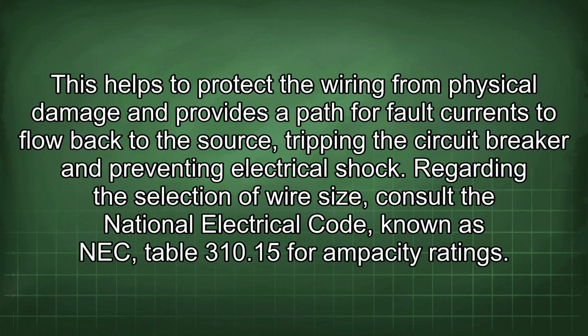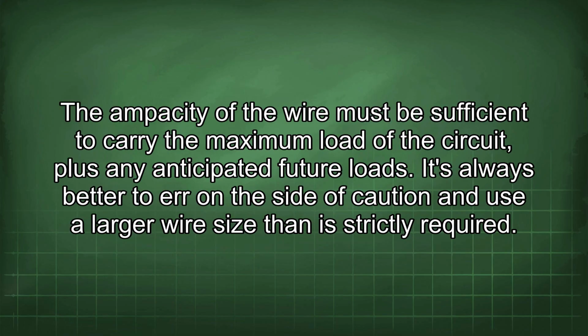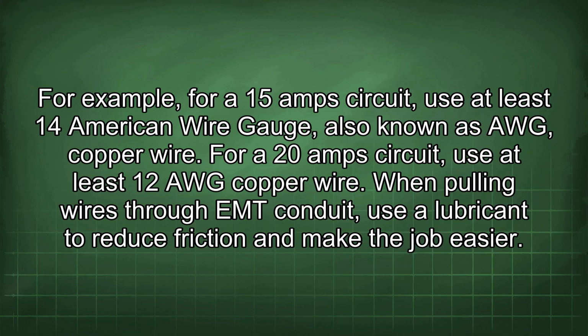This helps to protect the wiring from physical damage and provides a path for fault currents to flow back to the source, tripping the circuit breaker and preventing electrical shock. Regarding the selection of wire size, consult the National Electrical Code, known as NEC Table 310.15 for ampacity ratings. The ampacity of the wire must be sufficient to carry the maximum load of the circuit, plus any anticipated future loads. It's always better to err on the side of caution and use a larger wire size than is strictly required. For example, for a 15 amp circuit, use at least 14 American wire gauge, also known as AWG, copper wire. For a 20 amp circuit, use at least 12 AWG copper wire.